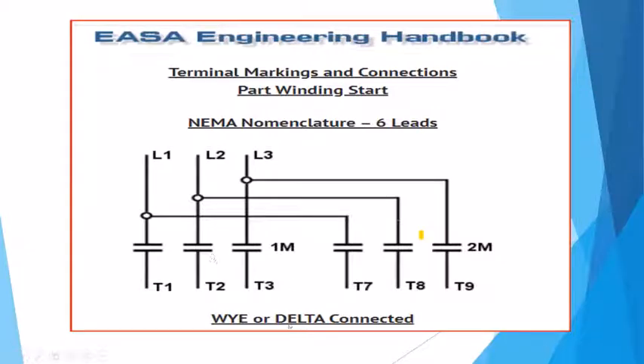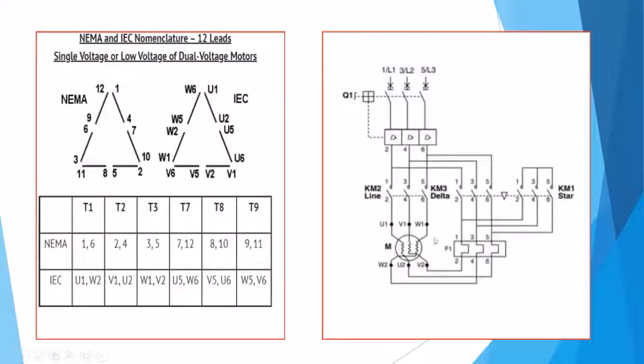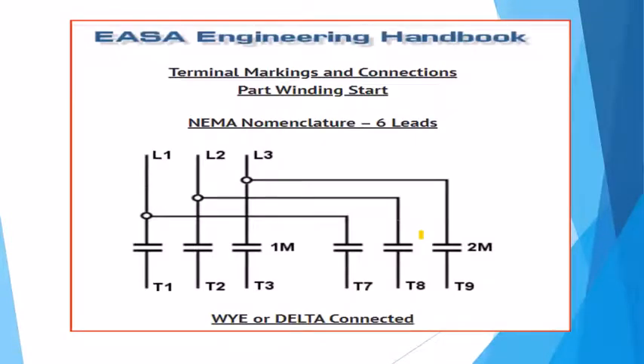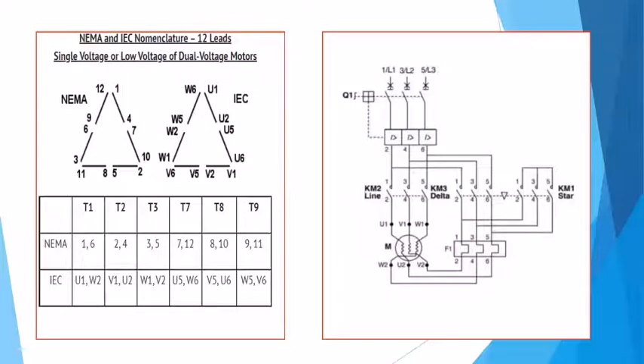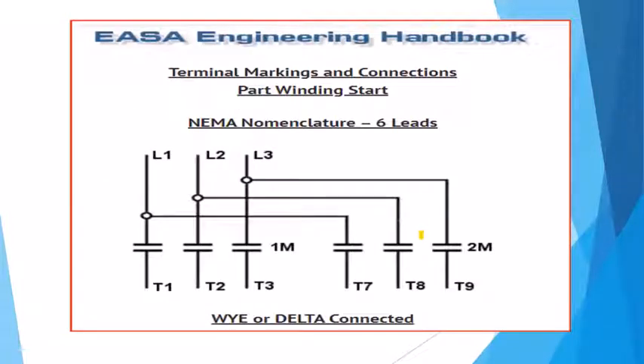They also do a connection for a Y delta, where you can connect the motor out and put 277 volts across the windings, what you'll normally be line to line after you go through your configuration of starter. And what ends up happening is that will give pretty good torque because you've got all the windings involved. So there's many applications you can do, either the part winding or the Y delta, just with contactors. And it drops the starting current from, let's say it was 500, down to maybe 250, 175, to start it, which helps.